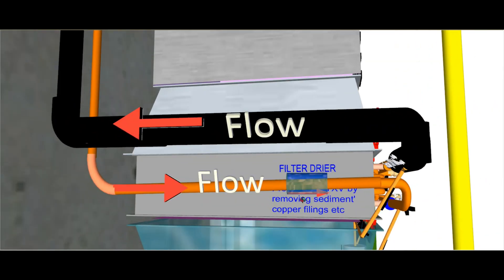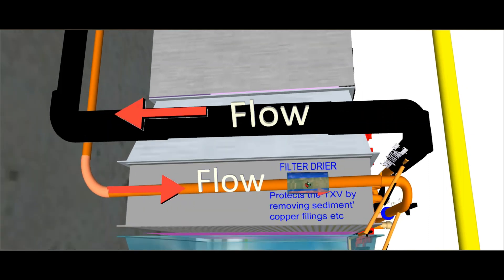The job of the filter dryer is to remove some condensation and also protect the TXV, which is the metering device, by removing sediment and copper filings from when you first install it, which always tends to happen with copper. So here it's going to turn and come around. Now I made a bit of a mistake—I should have just ended it there, so I put a little stop here. It's not going to go through here. It's got to go through the metering device first.